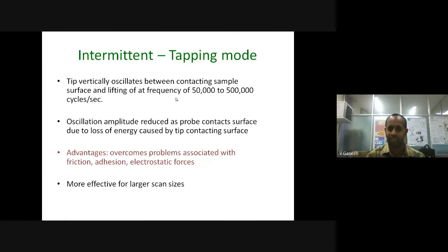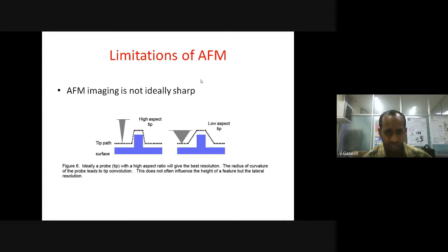Now the limitation of AFM is you need to have a very sharp and high aspect ratio tip like this, so that when you move this tip across the sample substrate, the images you get are very high resolution with striking structural features. If you use a very low aspect ratio tip, a blunt one, it would not give atomically striking features using AFM.